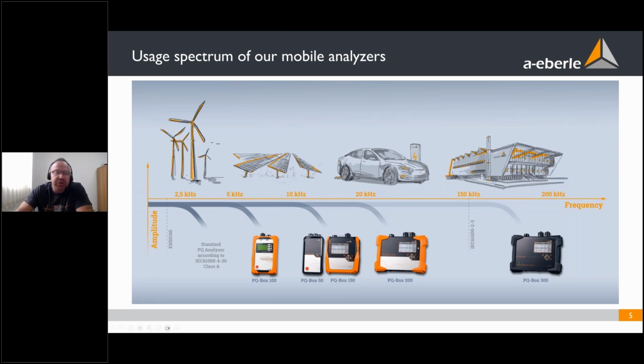So with the PQBox 200, the sampling frequency is 40 kilohertz. So we are limited to 20 kilohertz to see disturbances of voltage and current. And our high-end analyzer is the PQBox 300, and here we can measure online up to 200 kilohertz, and for permanent recording of all the superharmonics we have up to 160 kilohertz.